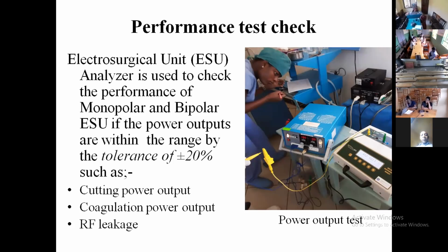The analyzer is used to check the performance of monopolar and bipolar ESU, ensuring power outputs are within range, with tolerances of plus or minus 20%, such as cutting power output and coagulation power output.